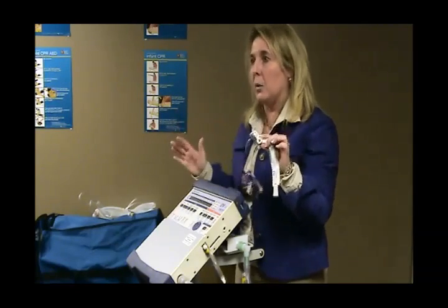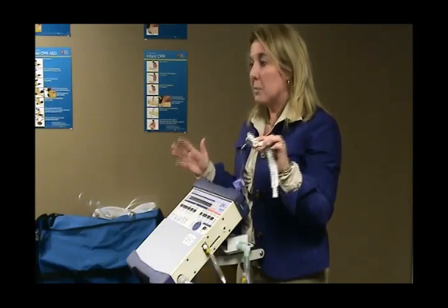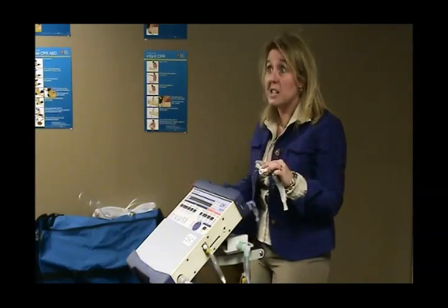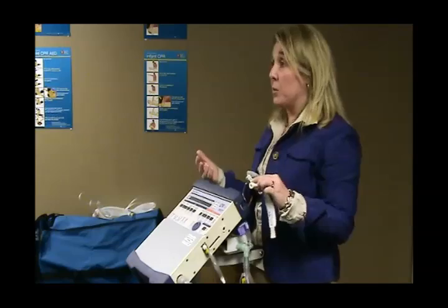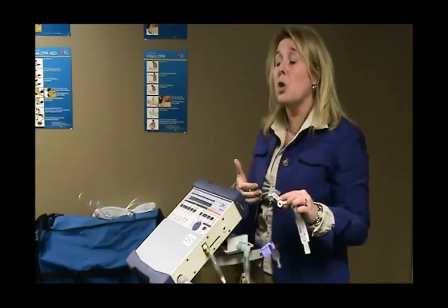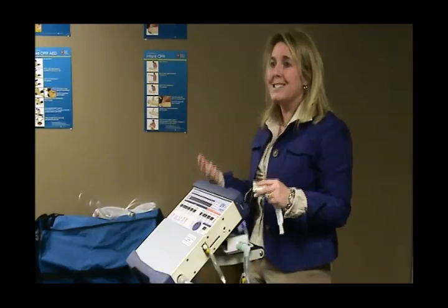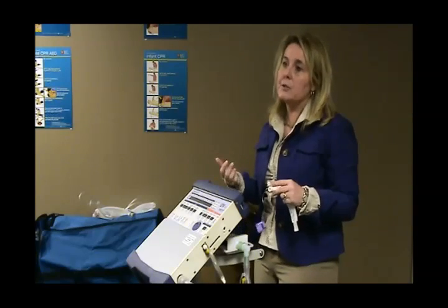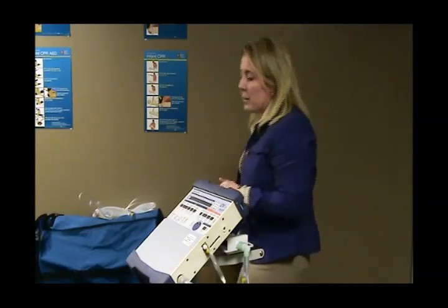It's very, very rare. Very rare. But I have seen it. So I won't say that there aren't exceptions to the rule, just get an order for it. Okay? Because if you shut off your low minute volume alarm, you may have disabled your secondary disconnect alarm, and that's dangerous. Okay, we'll talk more about that when we go through why.